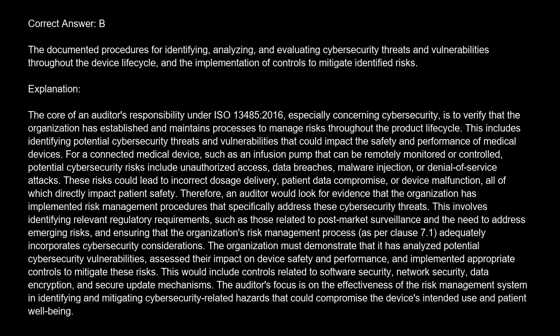Correct answer is B. The documented procedures for identifying, analyzing, and evaluating cybersecurity threats and vulnerabilities throughout the device lifecycle, and the implementation of controls to mitigate identified risks. Explanation. The core of an auditor's responsibility under ISO 13485:2016, especially concerning cybersecurity, is to verify that the organization has established and maintains processes to manage risks throughout the product lifecycle. This includes identifying potential cybersecurity threats and vulnerabilities that could impact the safety and performance of medical devices.